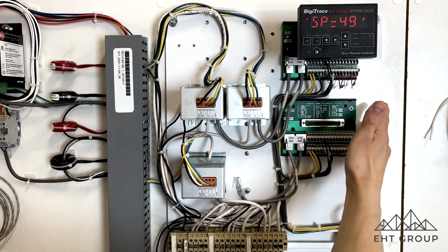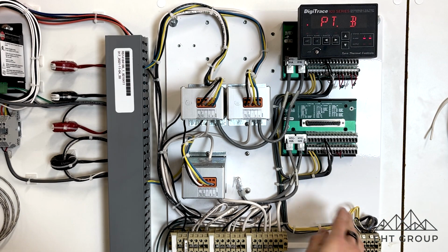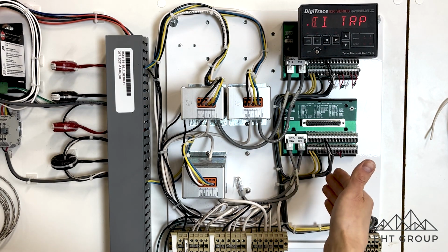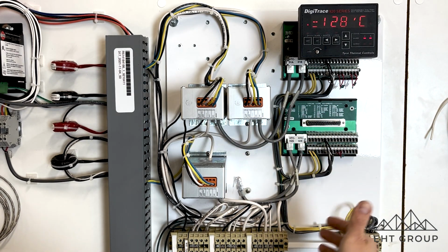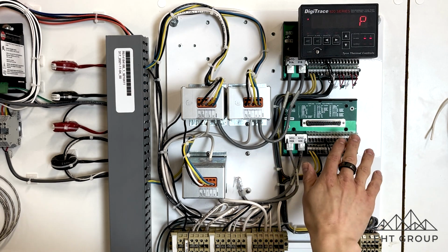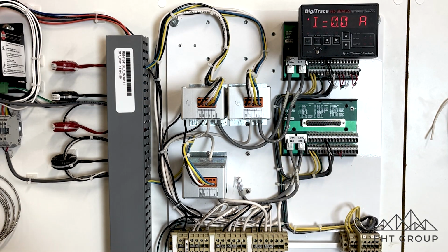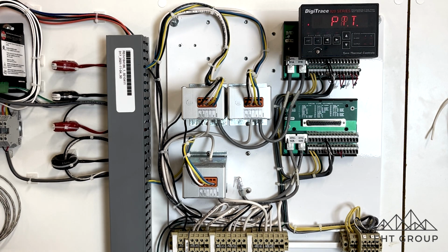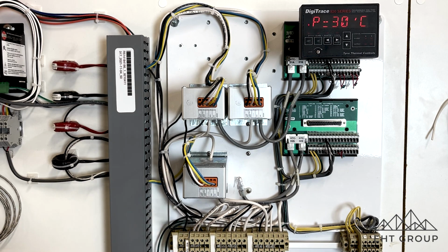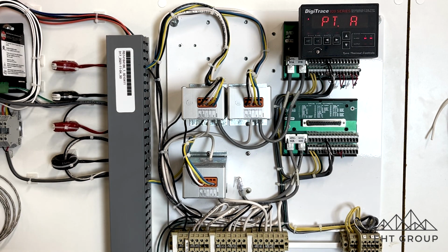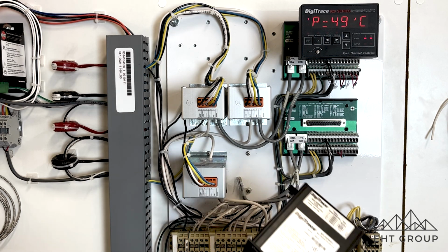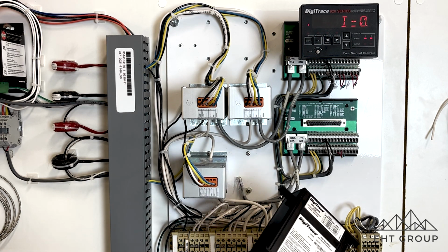So the control board is where we do all of our external wiring. Whether it be our common alarm wiring, our RS-485 communication, our external inputs, external outputs, or our RTDs, everything gets wired to this control board. The last thing I want to note is related to RS-485 communication. Some older heat trace control panels that get RS-485 communication, or if they introduce RS-485 communication at a later date, only some 920s are RS-485 communication compatible.